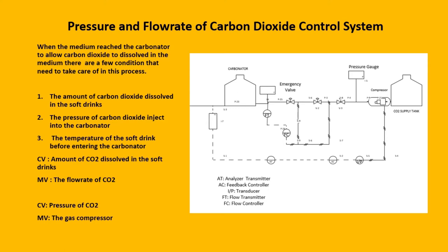The amount of CO2 dissolved in the soft drink and the pressure of CO2 will be the control variables, and the flow rate of the CO2 and the gas compressor will be the manipulated variables. When the amount of CO2 dissolved or the pressure of CO2 drops, the analyzer transmitter and the flow transmitter will send a signal to a comparator, and the comparator will calculate the error between the set point and the signal received. The flow controller and the feedback controller will monitor output and give a correct output to the valve and the compressor. For the pressure, there will be an extra transducer to change the milliampere signal into a pneumatic signal.